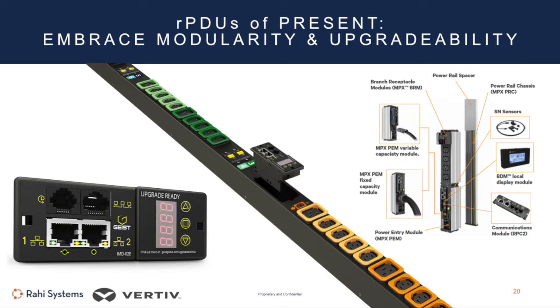So for instance, you can exchange a legacy card for a PDU that you bought a few years ago with an updated card that can provide enhanced functionality like some of the temperature sensor daisy chaining and such that we talked about earlier. And we can contrast that with a different take on it over here on the right, where you have PDU models where the PDU itself is essentially a modular bus bar, and a user can exchange different modules within the PDU to address different outlet types.